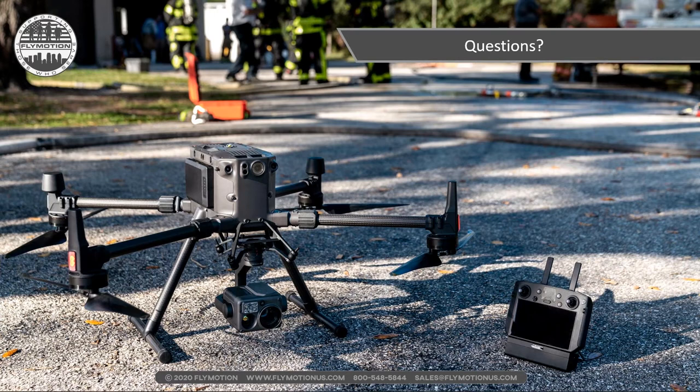Right. But what we teach is that anytime you're going to fly into a cloud that you suspect to be flammable, start upwind and approach from the area of least contamination toward the source. The idea being that at the source, at some point, you're going to have 100% LEL. That's where you have just the right amount of oxygen mixed with just the right amount of flammable.